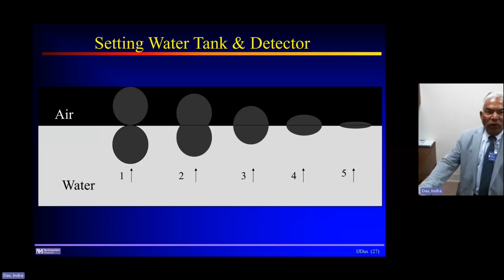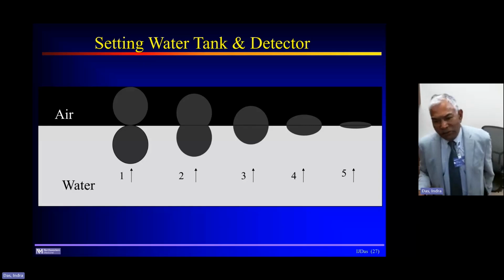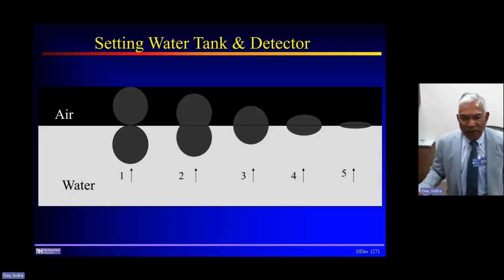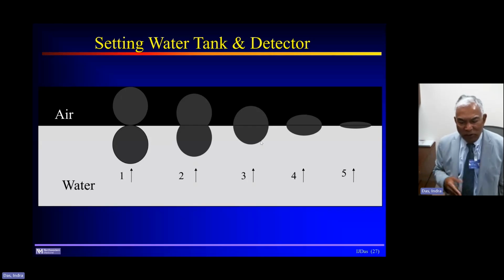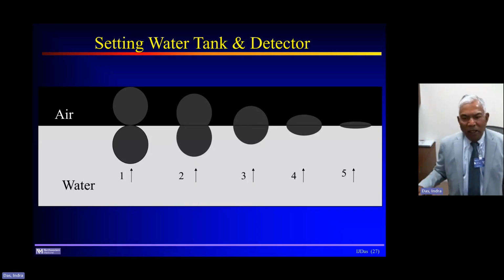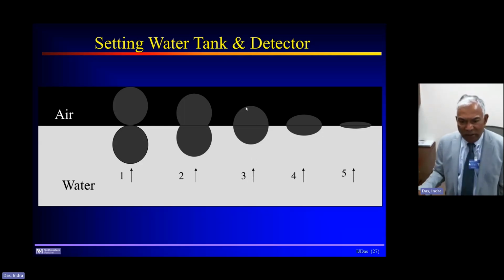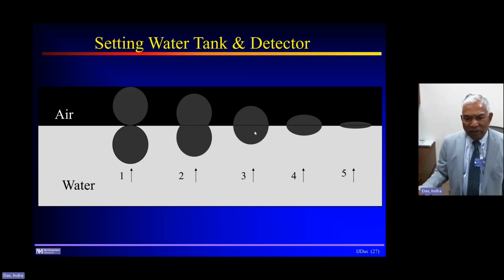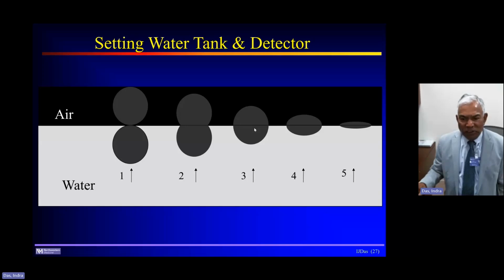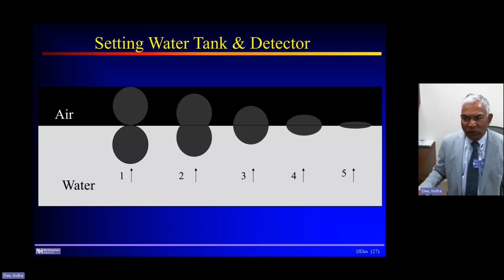Now, when you are setting up the water tank, obviously these are all standard common sense things, and these are all your board questions too. When you are setting your ion chamber, where you should set, whether you should set here, here, here, because if you go up and down and you look from the side of the tank, you may see these kinds of diagrams, and the right choice is that if you know that your detector is circular, then this is the right one. That means the center of your detector is at the center. So that's a choice that you have to make.